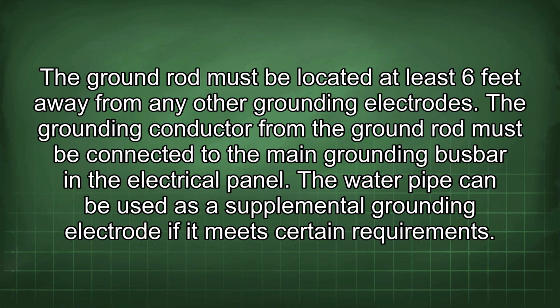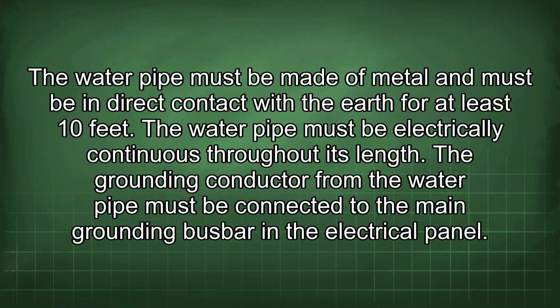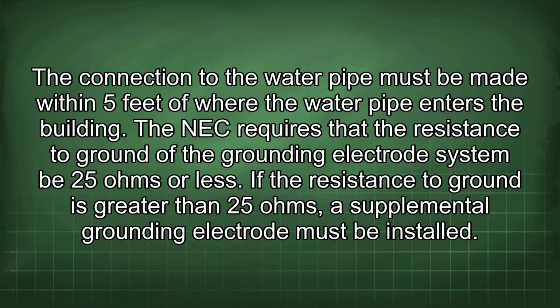The water pipe can be used as a supplemental grounding electrode if it meets certain requirements. The water pipe must be made of metal and must be in direct contact with the earth for at least 10 feet. The water pipe must be electrically continuous throughout its length. The grounding conductor from the water pipe must be connected to the main grounding busbar in the electrical panel. The connection to the water pipe must be made within 5 feet of where the water pipe enters the building.